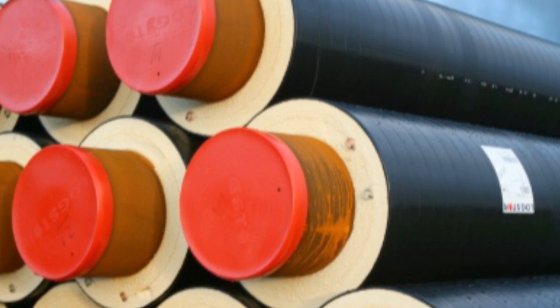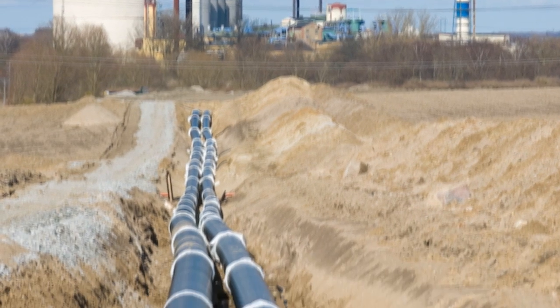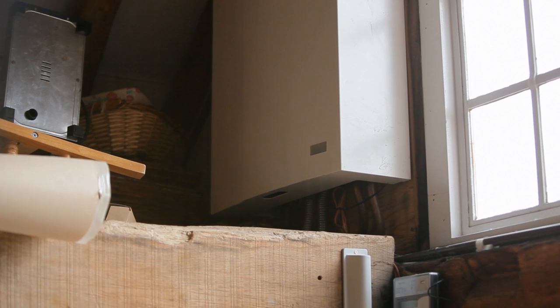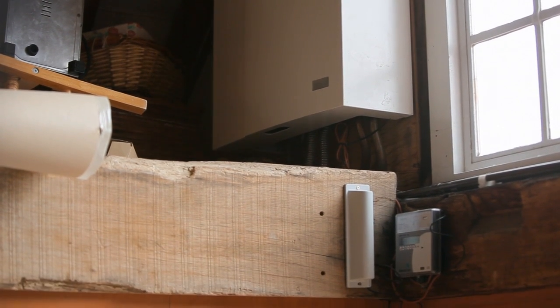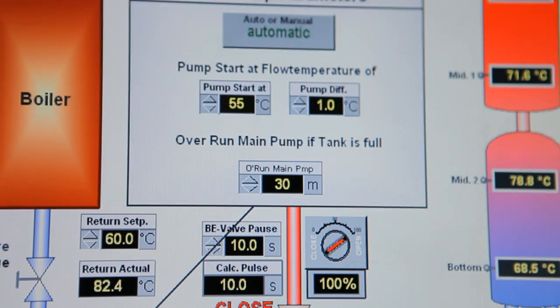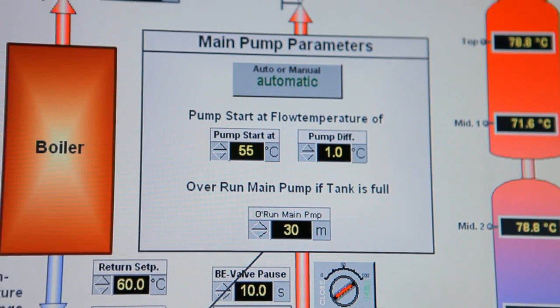The district heating system consists of a highly insulated network of flow and return pipes buried in the ground. These are referred to as the heat main. Water is heated by the central boiler and travels along the flow pipes, distributing hot water past all buildings that might be connected. In each building that is connected, there will be some sort of heat exchanger, where the heat from the flow pipes is transferred to the water in the central heating system of that building. Once the heat has been extracted, the cooled water from the main then passes into the return pipe back to the boiler to be reheated.